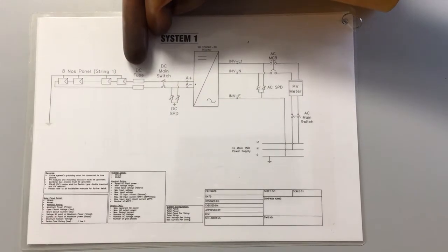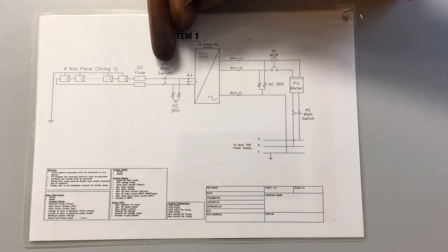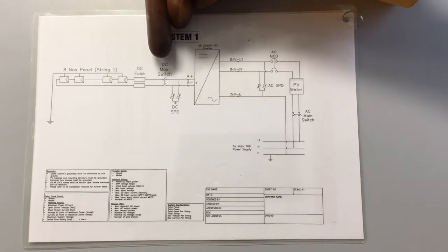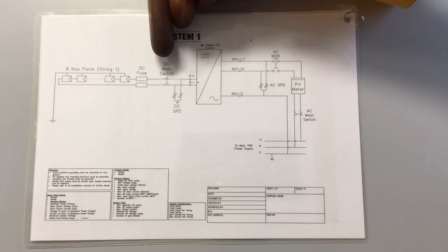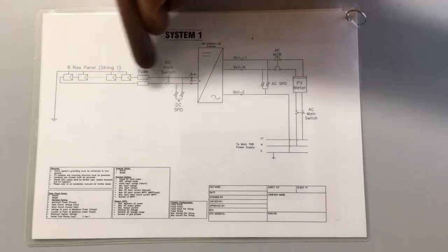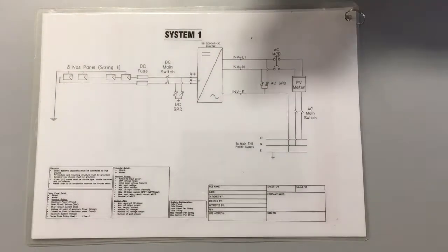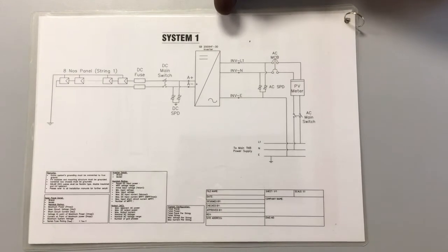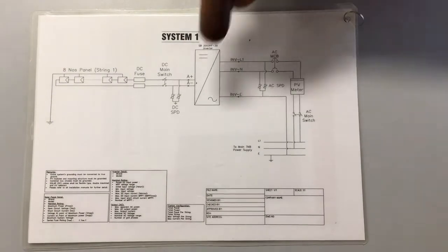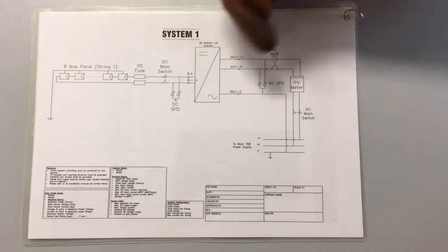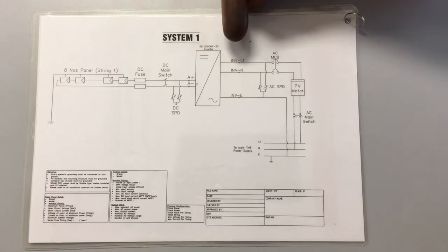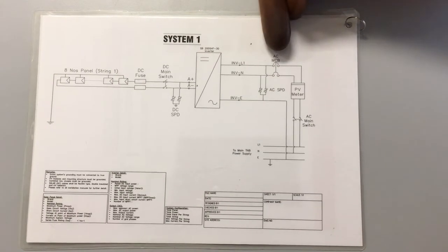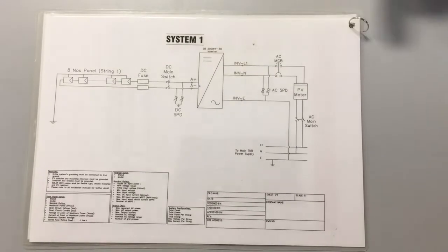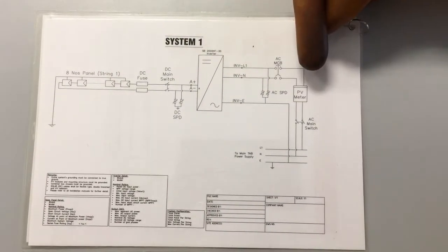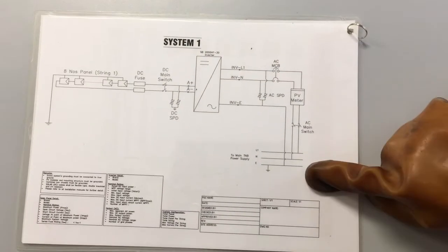For the fuse and the main switch, a fuse will blow if there is overcurrent, and the main switch we can use to do maintenance. We need to remember that even when the main switch is off, there will always be power coming from the PV module if there is daylight, if there is sunshine. So we need to be careful. There's still live voltage, no matter what you do at the main switch. Coming out of the inverter, we have AC supply. We connect it to the AC MCB and AC SPD in parallel as well, to protect if lightning comes from the other side, and then the PV meter, and then the main switch before it goes to the grid.